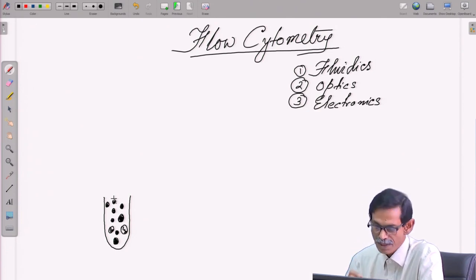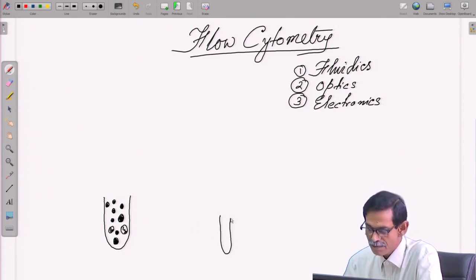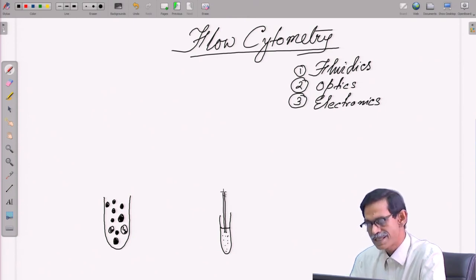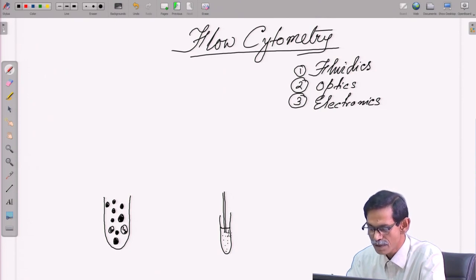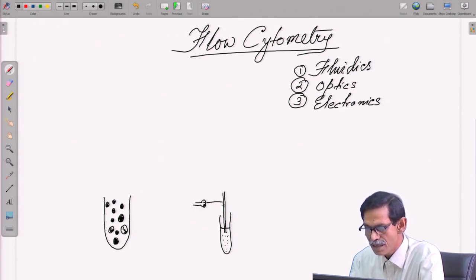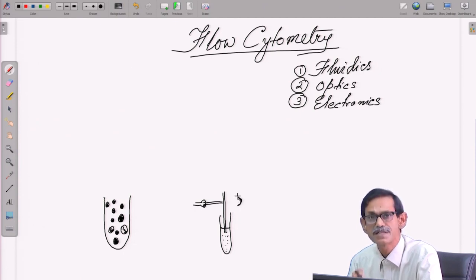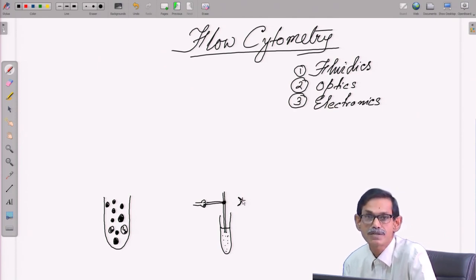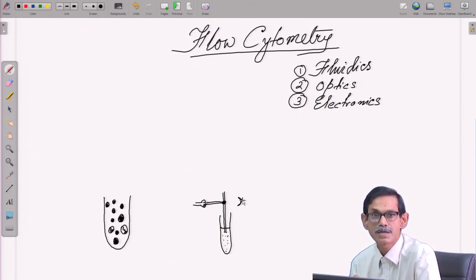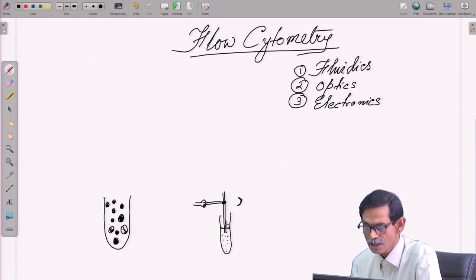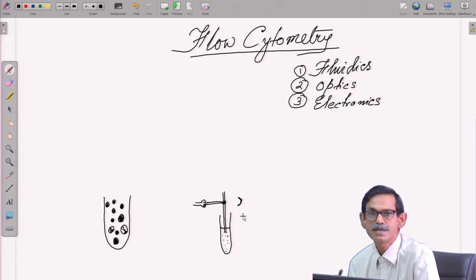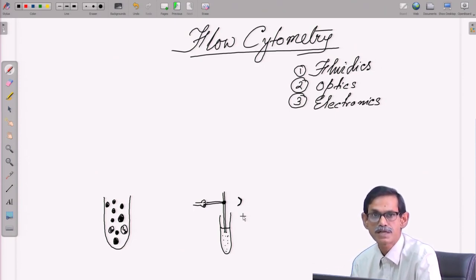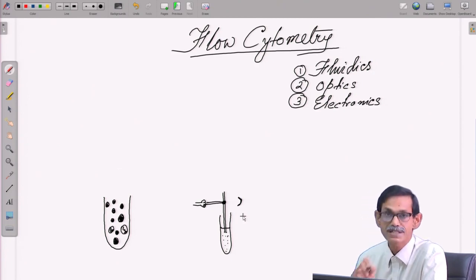In a bacterial counter the idea is very simple. You take bacteria in a tube — there are a lot of bacteria. If you have a capillary there and you suck the cells, the bacteria will move from solution through this pipe. If there is a light source and a photomultiplier tube — as soon as one cell comes there will be a shadow, and that shadow will be counted. That is very fast; you do not have to count by hemocytometer. Each cell will go, each shadow will be counted, and finally after a certain time you can say in one ml or 10 or 100 microlitre how many cells there are. That is how a bacterial counter works.